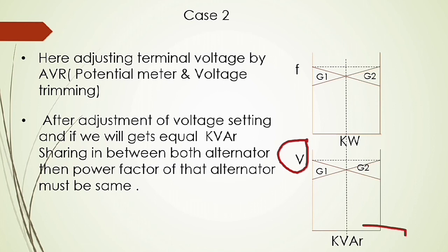After adjustment of the voltage setting, if we get equal kVAR sharing between both alternators, then the power factor of those alternators must be equal, must be the same. This is the condition: if we share the kVAR equally, the power factor of the alternators must be the same. The only condition is that the sharing of reactive power should be the same for both alternators.